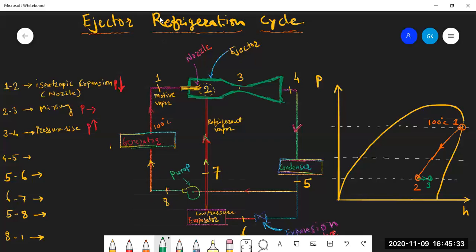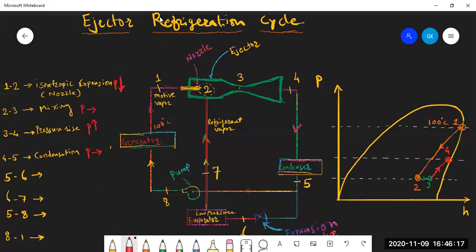In three to four there is a pressure rise because of the shock wave and the gradual increase in area. Then four to five is the condensation process in the condenser. During condensation, heat is rejected at constant pressure, so pressure remains constant. Heat is rejected to cooling tower water or any system that absorbs heat — it may be air-cooled or water-cooled.